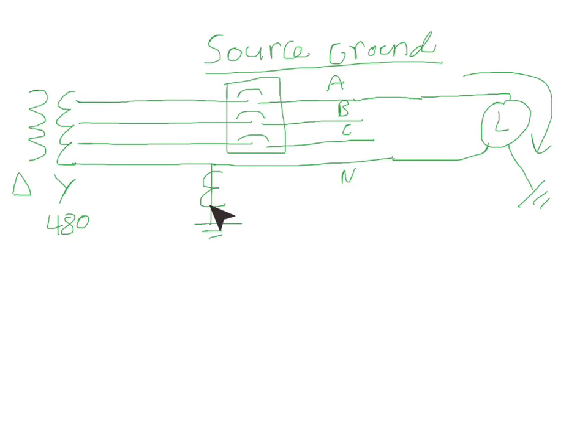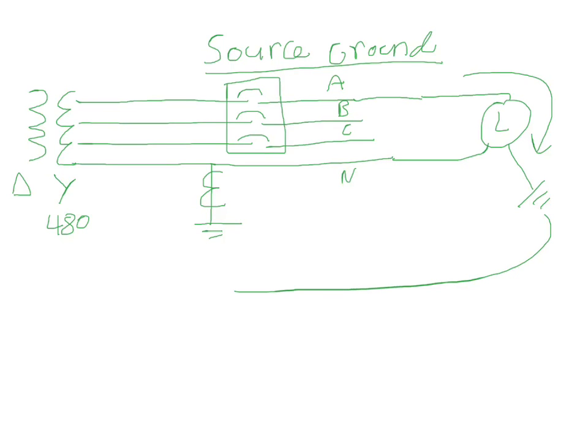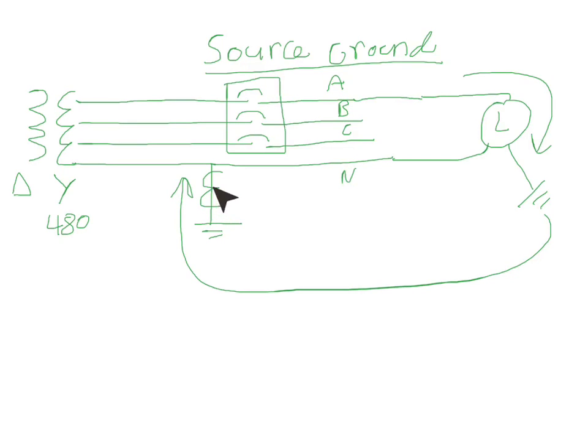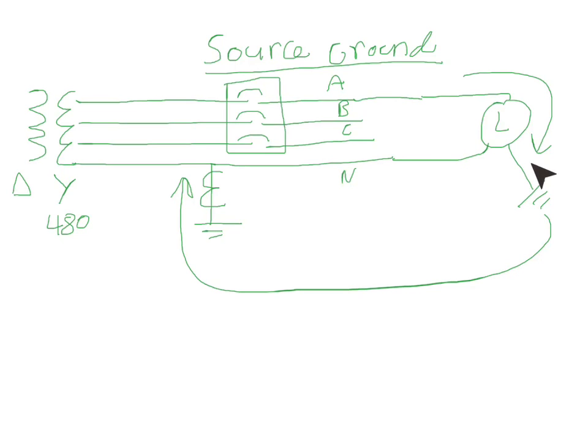And then go back to our transformer. So that's how the current would travel - it would go like this, come up here, and our ground CT would pick it up. This ground CT is wired to the breaker and the breaker would trip. Okay, now if there wasn't a ground fault here, the current will just continue to run on the neutral here.